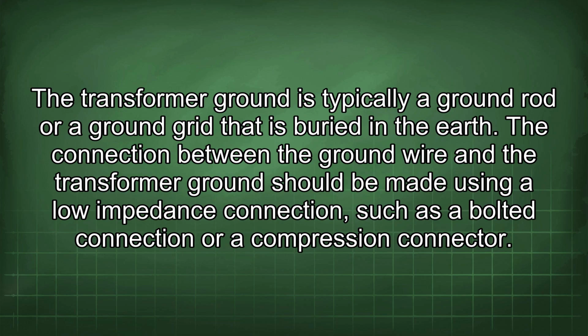The transformer ground is typically a ground rod or a ground grid that is buried in the earth. The connection between the ground wire and the transformer ground should be made using a low impedance connection, such as a bolted connection or a compression connector.